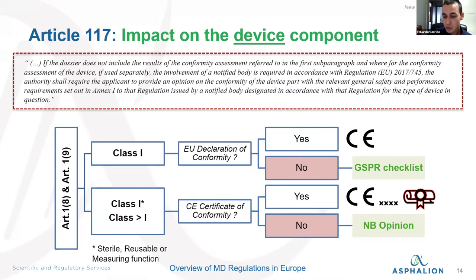In the case of class 2A, 2B, or 3, you had to provide the certificate of conformity given by a notified body, or you could provide the GSPR checklist, but nobody was checking the requirements of the device. Now what has been implemented is that a notified body has to assess your device, even if your device is not undergoing CE marking. This is the new change of the regulation.